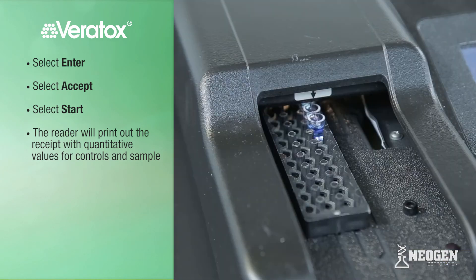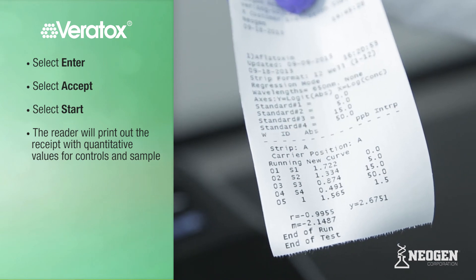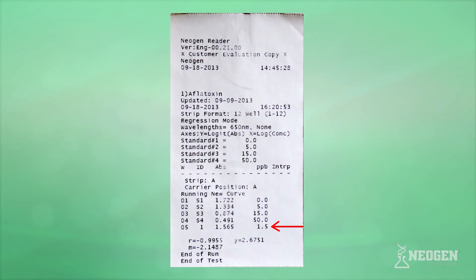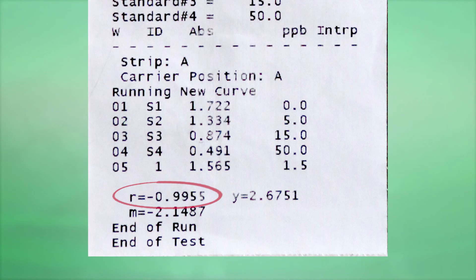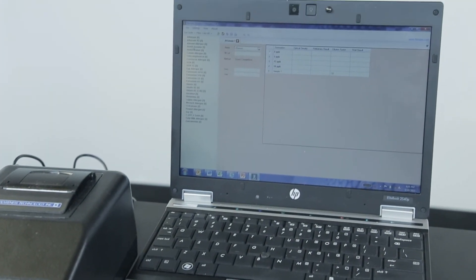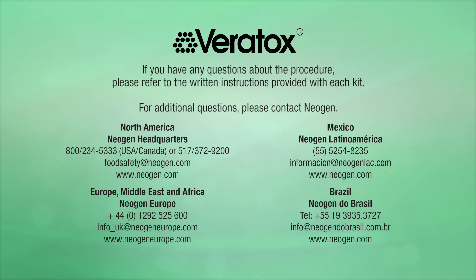The reader will print out a receipt with quantitative values for controls and sample. The middle column is the absorbance of each well, and the right column shows the exact parts per million or parts per billion of the controls and sample. Our sample today was 1.5 ppb. Below the columns, you will see the R value; if this value is less than negative 0.98, the test is invalid and must be run again — this value ensures the test performed correctly. Neogen also offers an optional Veratox for Windows software program that reads and logs test results electronically. If you have any questions about the procedure, please refer to the written instructions provided with each kit or contact Neogen.